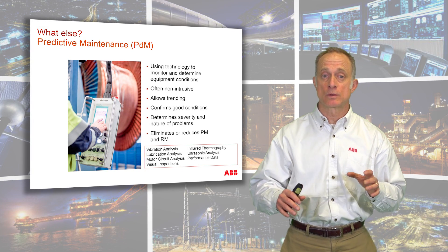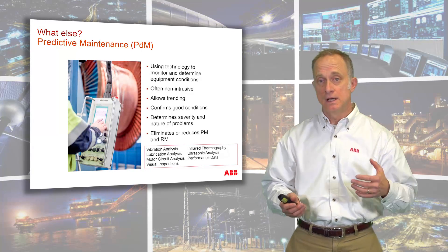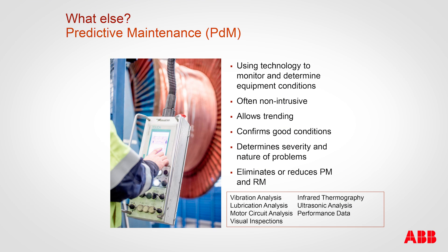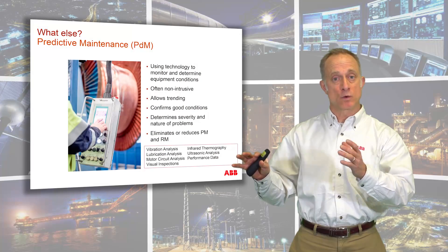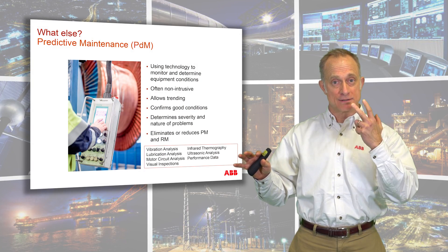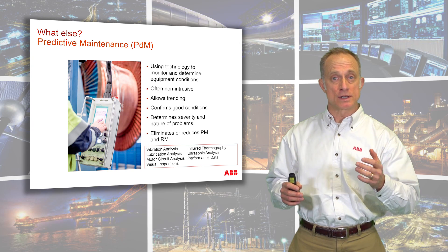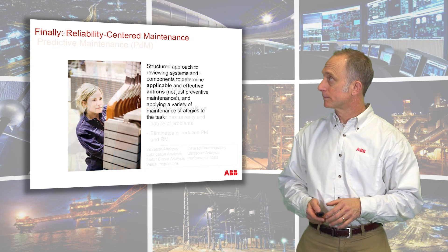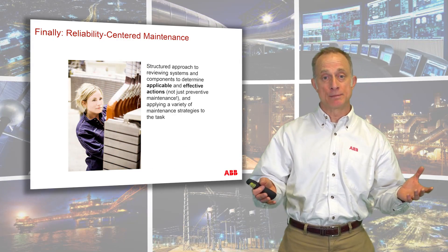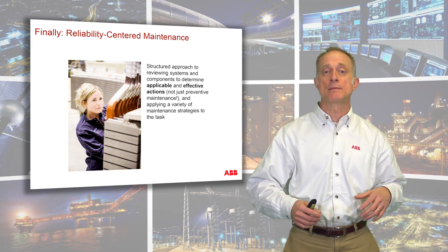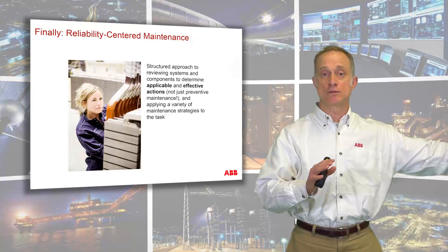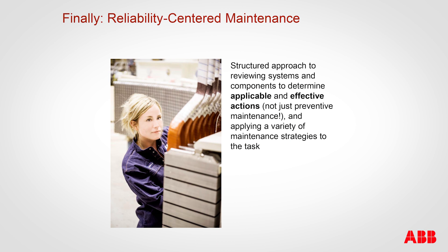There's also predictive maintenance. This is when we use a variety of technologies such as infrared, thermography, or lubrication analysis — different kinds of technology to assess a piece of equipment even while it's in operation — that might be able to determine certain things on that piece of equipment that we can't see with our naked eye or can't hear, that will alert us that something needs to be addressed. Then finally we get to reliability-centered maintenance, which takes advantage of all of those things and only chooses the right approach for the right piece of equipment.